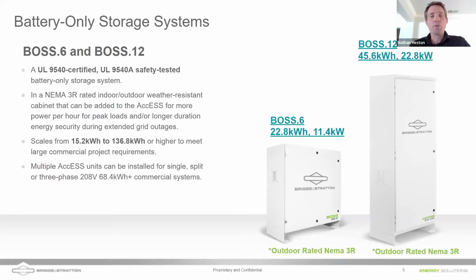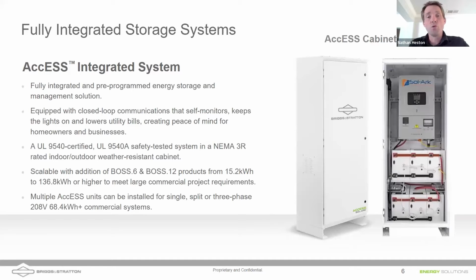I do want to point out that though the SimpliPhi and the Phi batteries are not outdoor rated, we do have NEMA 3R enclosures, and these enclosures have the ability to offer heating that can be built into the BMS and directly heat the batteries in cold weather environments. These cabinets can also be utilized to provide an AccESS system, and this is a complete, almost plug-and-play system that we can integrate with Sol-Ark inverters. And you see that on the right paired with an 8K Sol-Ark and our communicating batteries there. It's a 9540 certified system, and we can scale these up to 137 kilowatt hours, so fairly large systems.